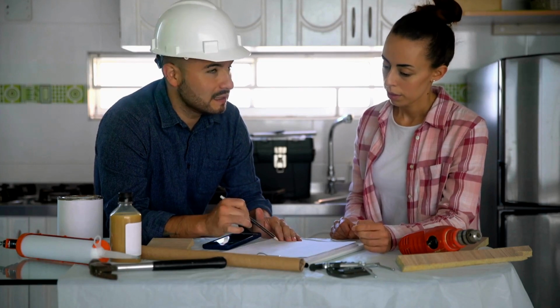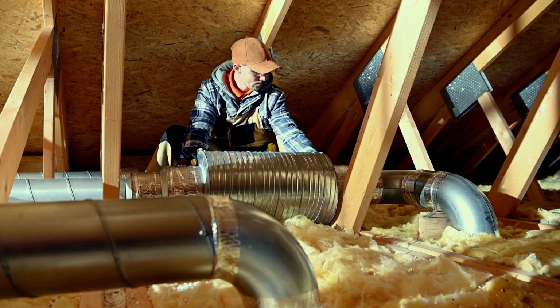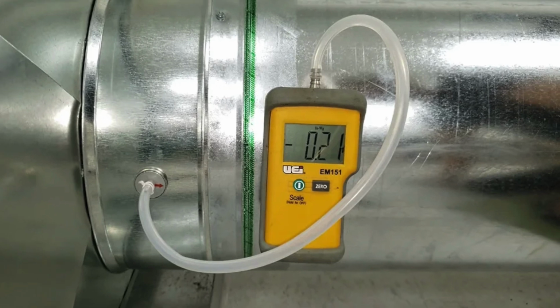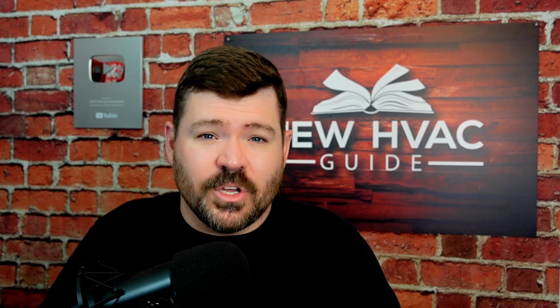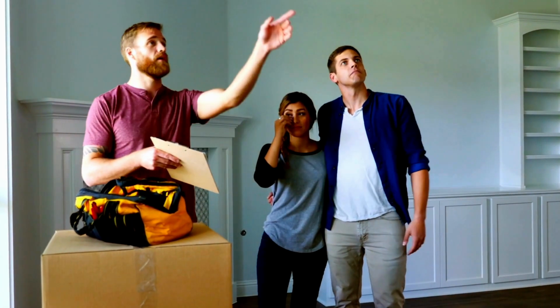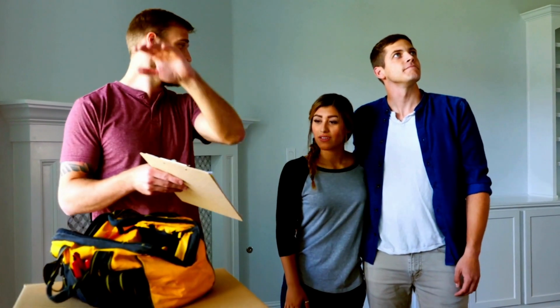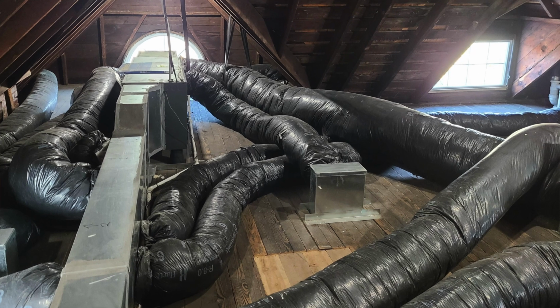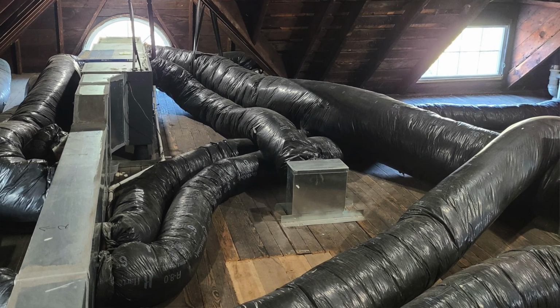They came out to your home and they should have inspected the ductwork. They should have checked static pressures at least after the product was installed. But, you know, a before would be nice, right? If the system still can run, you could throw your static meter on there. At bare minimum, have someone go around and count the number of vents and look at the size of the ducts going to those vents, making sure the ducts are somewhat decently installed so that we don't have huge amounts of static or big turns in the ductwork or whatever. Just overall, kind of looking at the job.